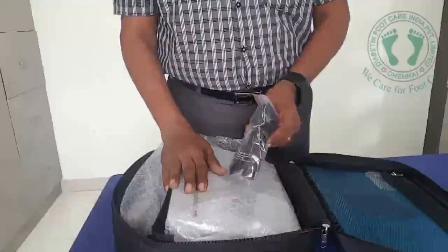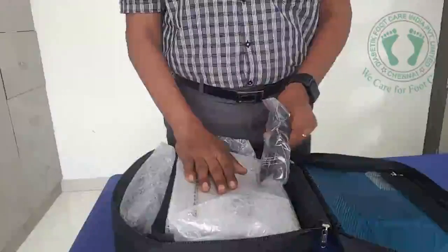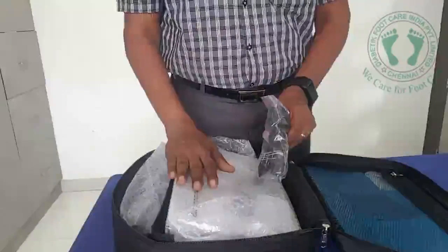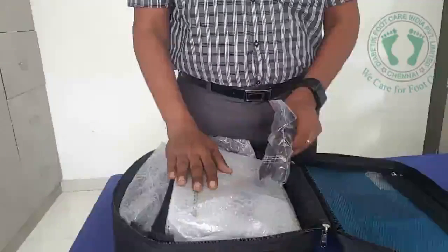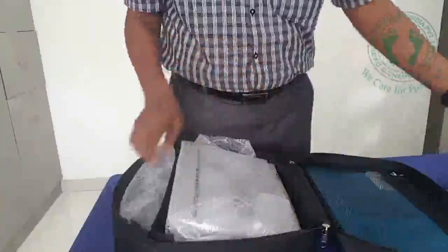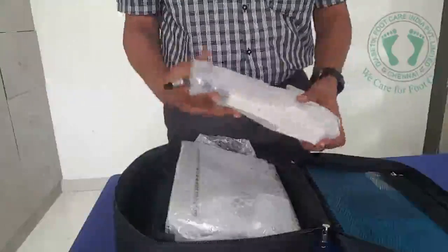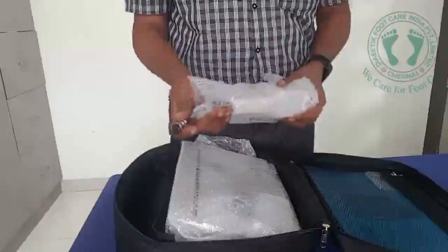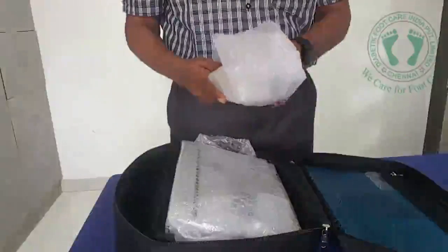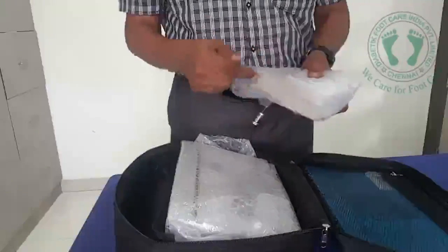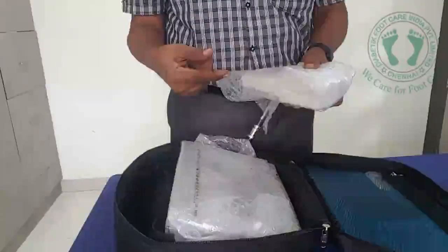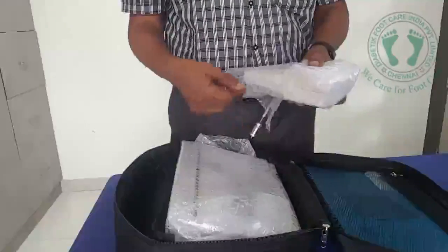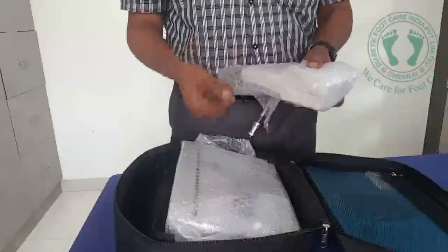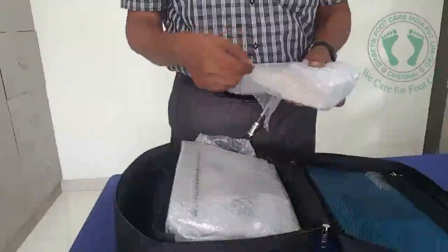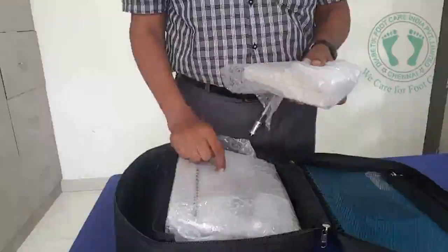So 230 volts and 110 volts are the two standard models available with us. If somebody wants a different voltage, then we can supply it. This is the vibration probe. You have a tip here, and that tip is tested on the patient. The tip generates the vibration. Based on the intensity of the vibration, the patient has to say whether he is feeling the vibration or not. Based on the value displayed on the device, we can interpret the output.